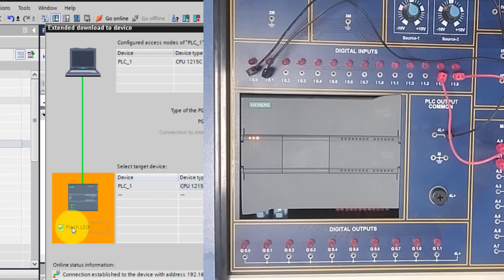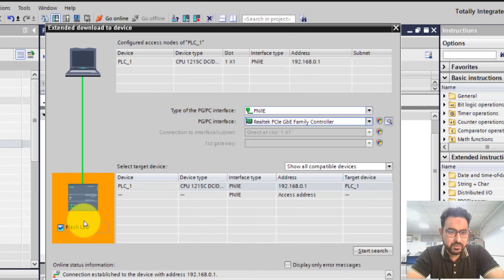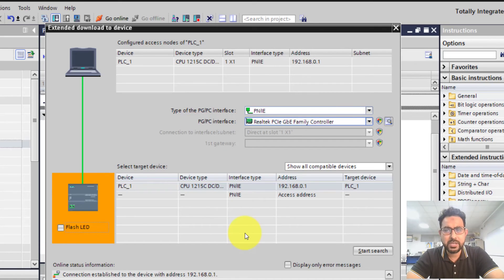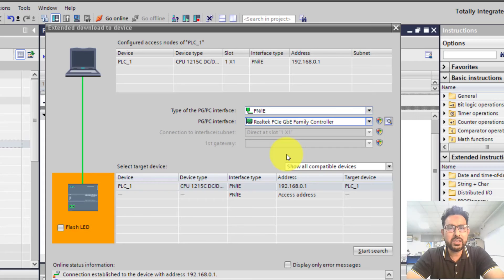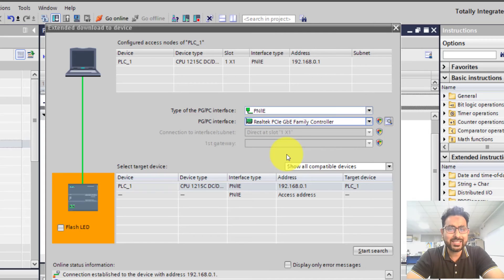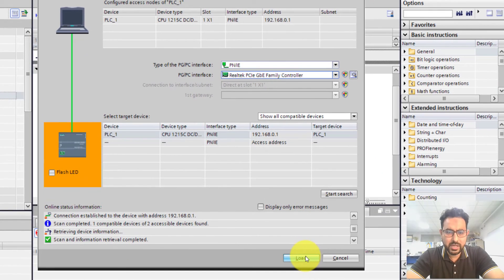You can click 'Flash LED' to confirm that the lights on your PLC are flashing, verifying the connection. If for the first time your PC cannot recognize the PLC, it may be because your Ethernet card has a dynamic IP address. TIA Portal will offer to assign a static IP address automatically, so you just need to allow TIA Portal to fix an IP address for your PC and it will connect with the PLC.